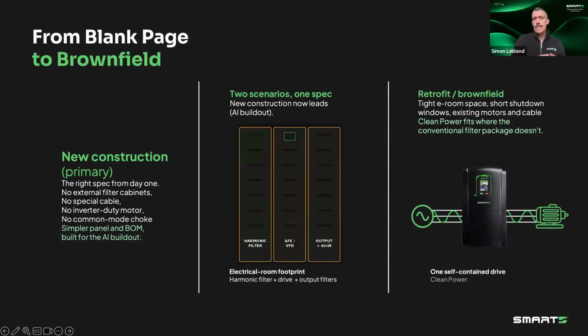I've talked about it, so you get applicability of the solution both in new construction, where you can simplify your specification by not requiring any external filters. So whether it's an active filter on the grid side for harmonics or a choke on the motor side, just simplify to one product. You won't have surprises. But it's also great in retrofit scenarios. If you have installed, for example, passive harmonic filters and you're getting resonance issues and you need to retrofit because of the problems they bring, then you have one self-contained drive that can replace that whole filter cabinet and the drive cabinet. So a much smaller footprint for these retrofit projects as well.